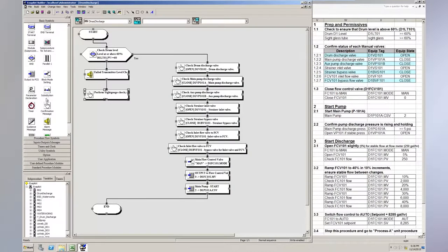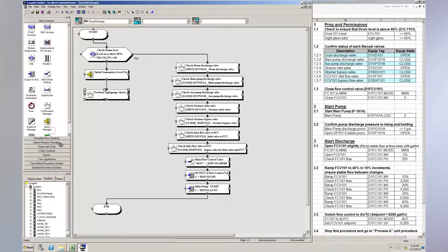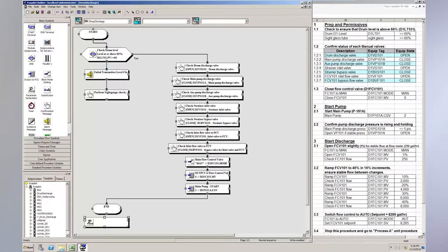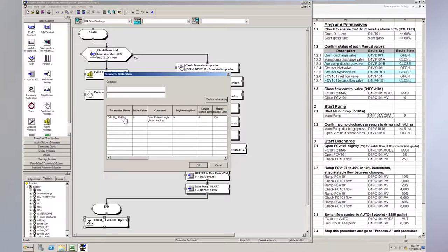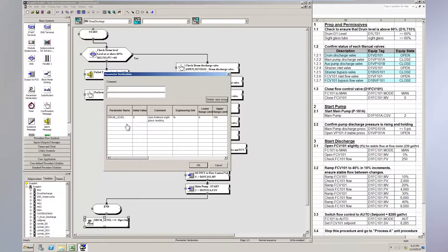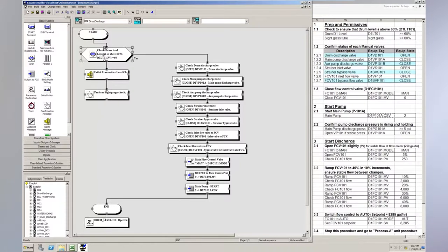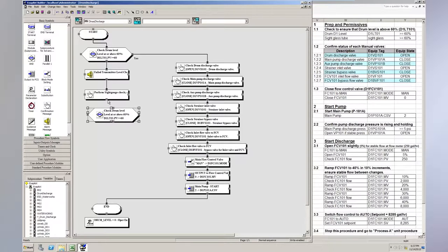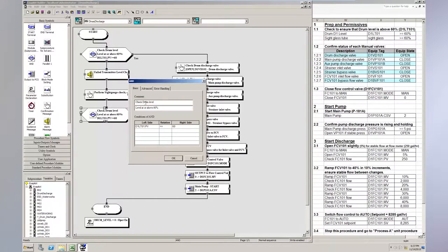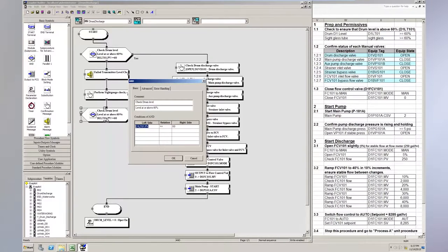And then I can drag and drop on a parameter declaration down here below. I can actually place it anywhere on the page. I want to put it down here below the end block. If I double click on that, then I get a pop up here. And I can now enter in the variable that I want to write to. So this variable here is going to take the input that the operator is going to enter and store it. Because then I'm going to use that variable as another check. Just like we did on the drum level check from the transmitter. We're going to do another check off the operator input to see if it passes the same criteria. Just because the operator entered it doesn't mean it's an automatic pass, right?